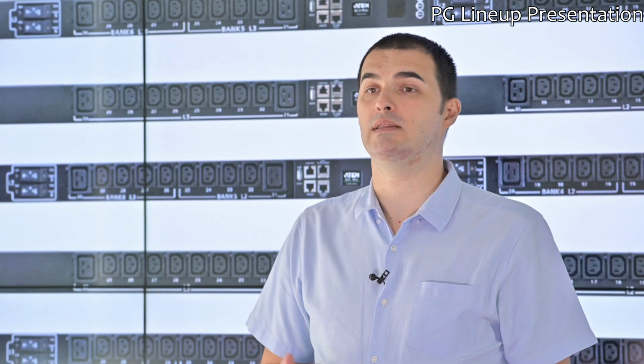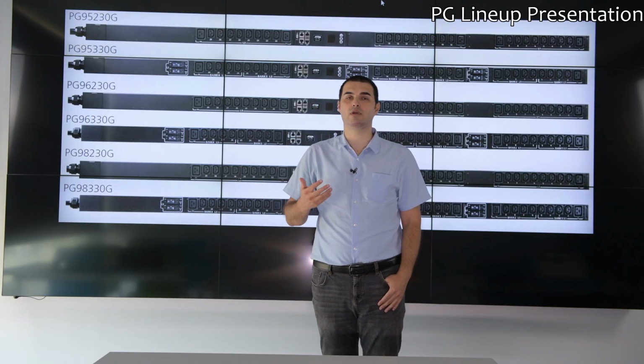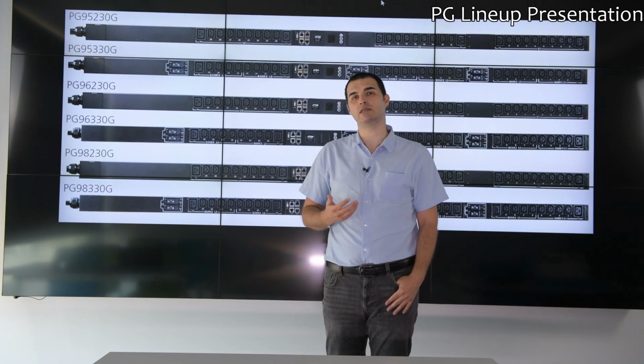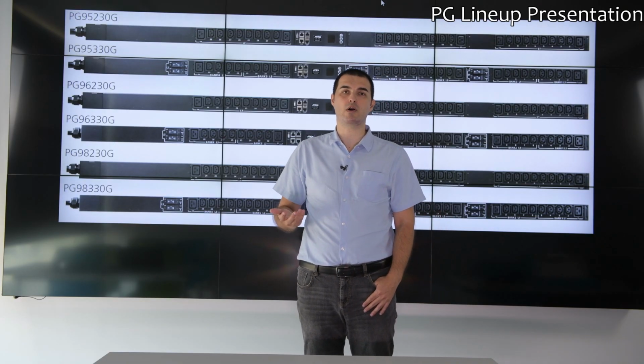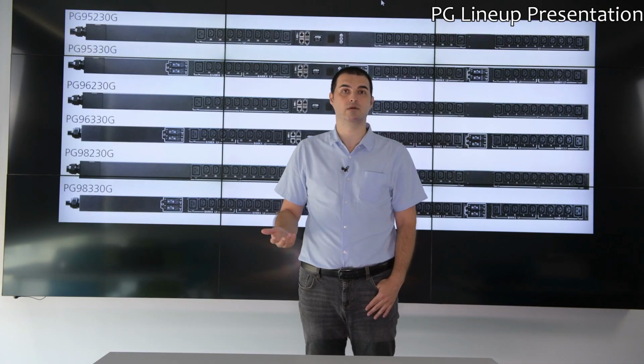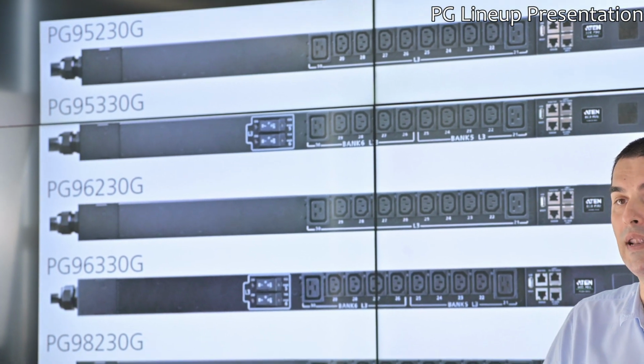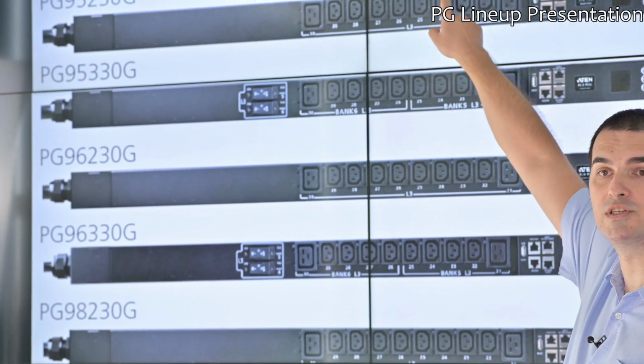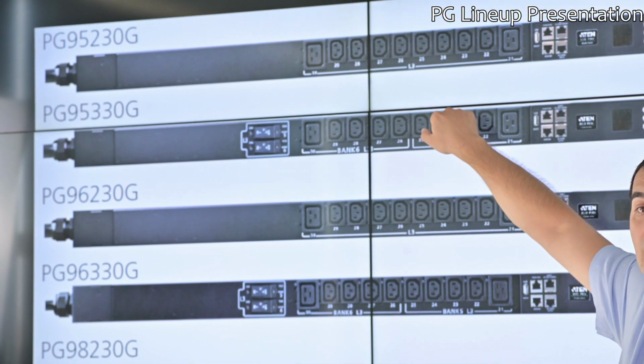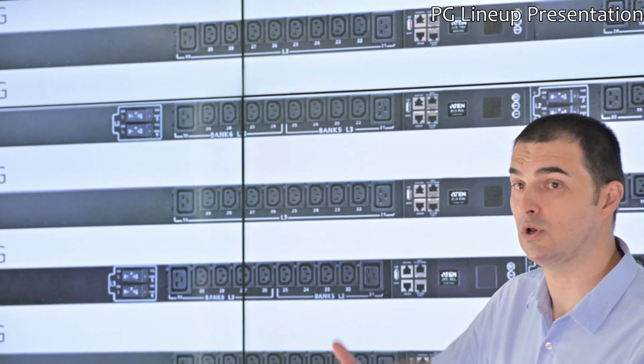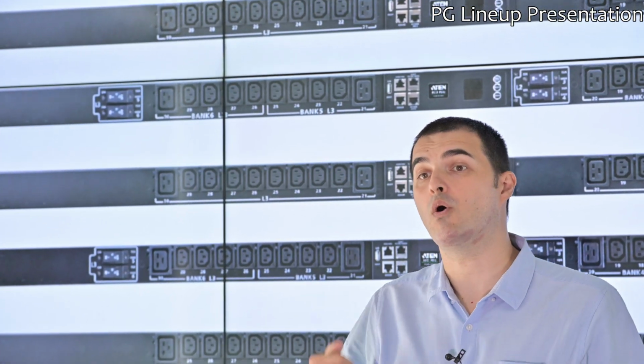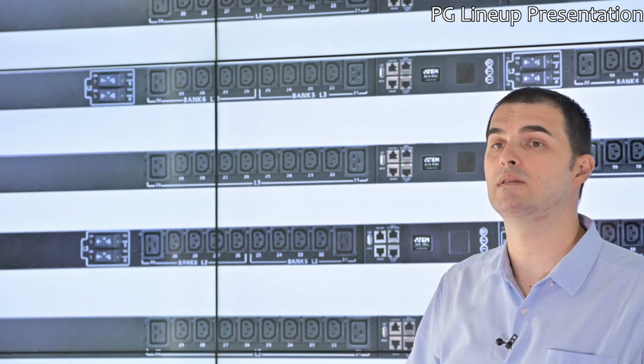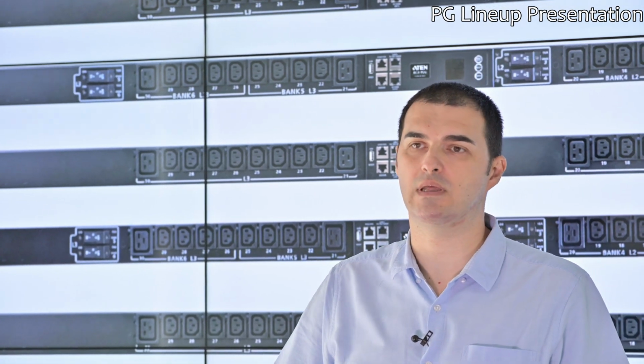The PG line consists of three subcategories: PG95, PG96 and PG98. Each of those have two models inside, 230 and 330. 230 means 16 amps, and 330 is a more powerful equipment, 32 amps. So let's recap: we have the 95 series, with 16 amp and 32 amp versions. These are metered PDUs, so these two will tell me on every single port what is the current consumption, the volts, the amps and the wattage.